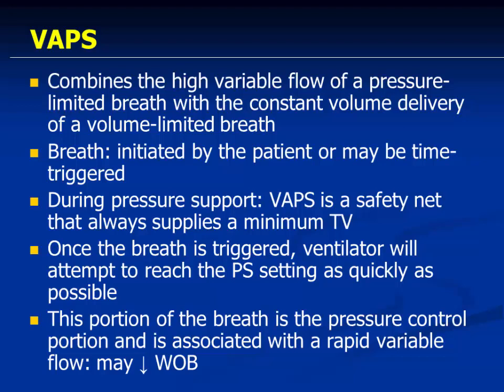During pressure support, VAPS is a safety net and always supplies a minimum tidal volume. So in a spontaneous breath, you switch on the VAPS, and it works as a safety net. If the patient is taking less than what you have set on the machine, it will pull up that breath up to that tidal volume. So it will work as a safety net. It will guarantee a minimum tidal volume.